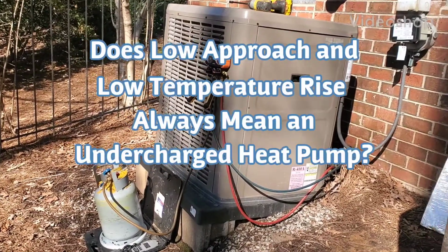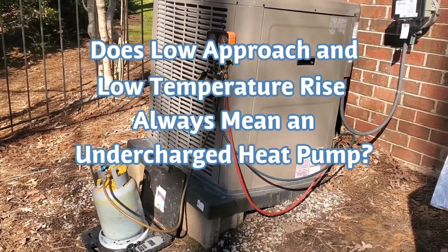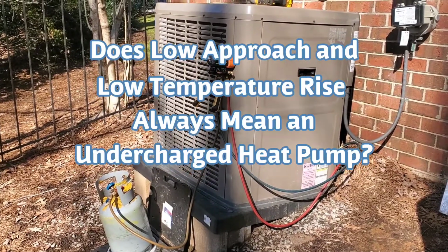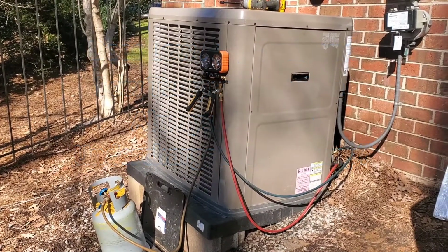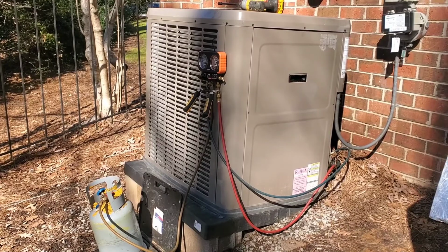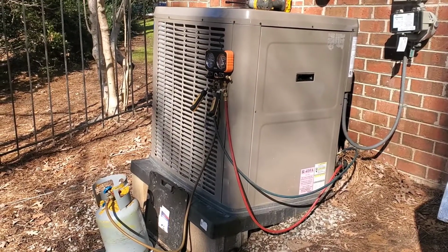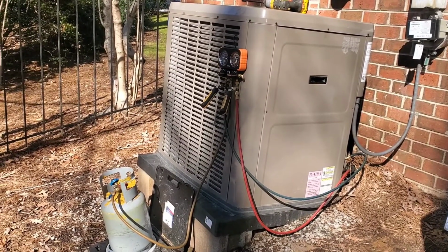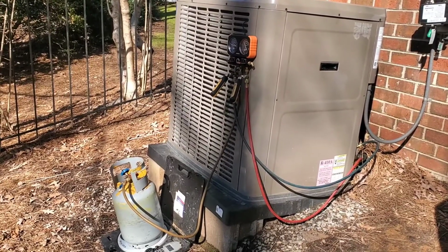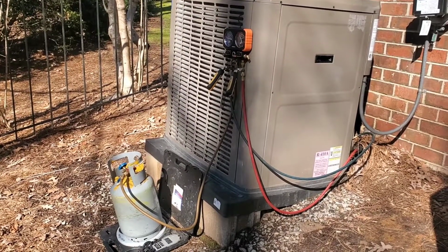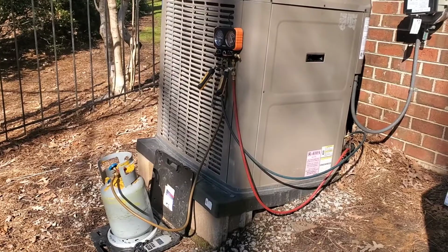Hey everybody, just want to share a valuable lesson that I learned. So I was charging this unit, it was a little bit low. This is a heat pump in heating mode. And I was looking at MeasureQuick, and I was looking at things like approach temperature, delta T, the typical things that you do when you're charging a heat pump in heating mode.